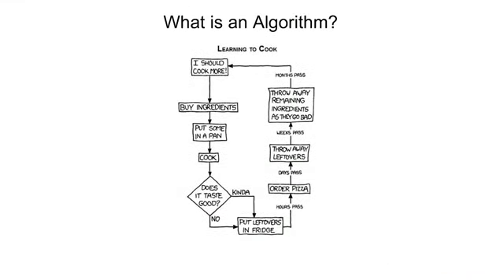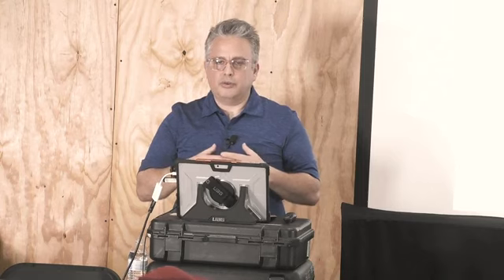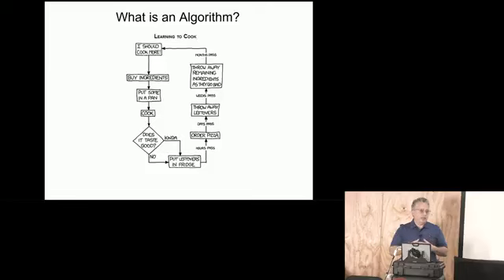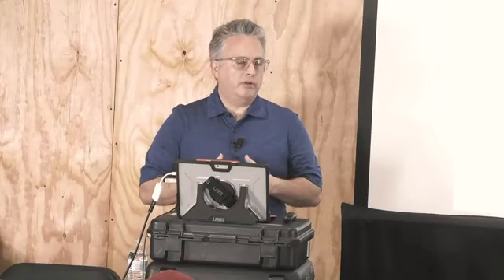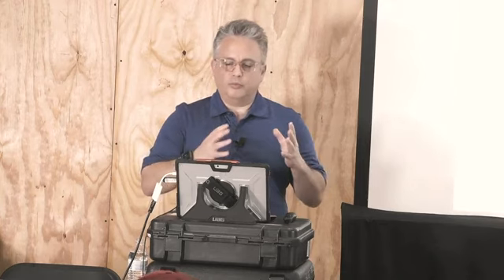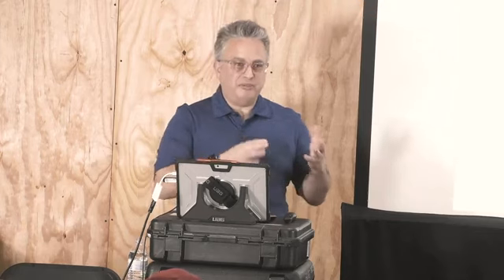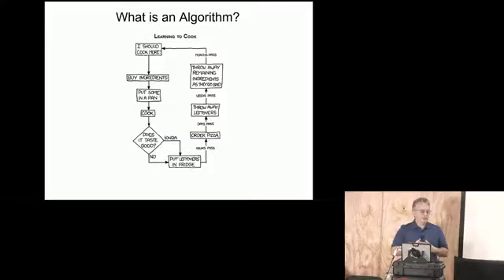So what is an algorithm? Well, basically, it's just a set of instructions. If this, do that. And the best analogy I can give to that is actually a story. I was called out on an 8-story hotel in Dallas, Texas. It was the summer that we had over 100 days with 100 degrees, and the system wasn't keeping up. The VRF system was cooling the common areas. And so I got called out and looked at the remote control, and it said 74 degrees. They wanted it at 72. And it was a little uncomfortable, slightly, not like the lobby.